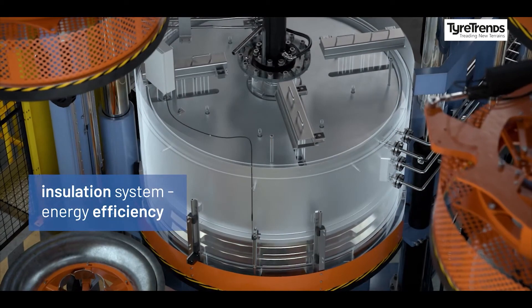The main thing we're looking at with customers is definitely ways to make the machines — if we're talking about a steam press — as efficient as possible. We've been analyzing the complete press, analyzing the piping, trying to figure out where the main areas for saving are. It's like our house: what do you insulate first? Roof and windows. We're looking at where the most heat loss is and testing with certain types of insulation to reduce that heat loss around the piping and the top of the press where steam is escaping.